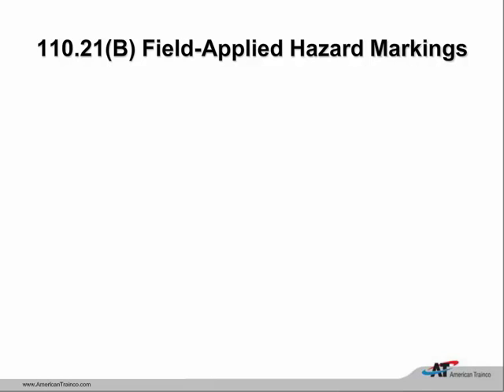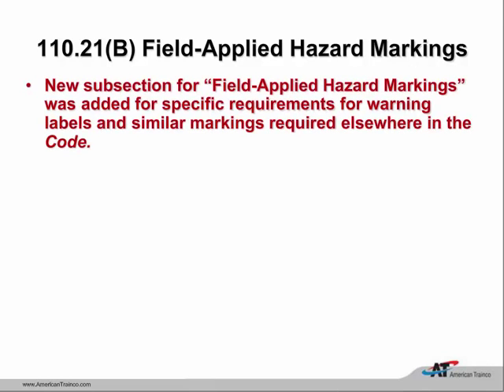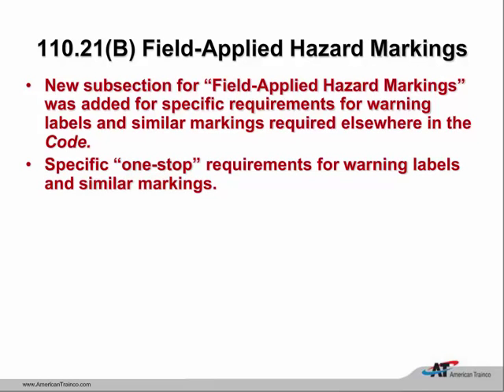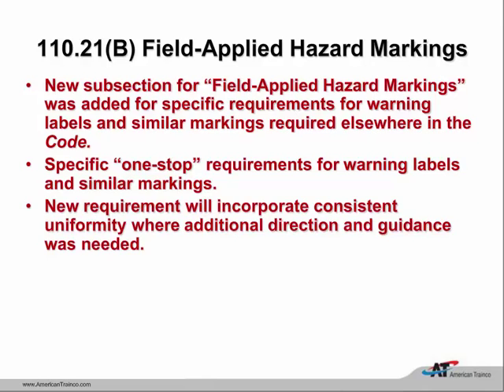In conjunction with 110.16, we saw 110.21B as a global change: field applied hazard markings. This is definitely going to coincide with the ANSI standard Z535 for labels. This now covers any label—not just arc flash hazards. It might be a voltage hazard or any hazard in your facility. One-stop shop is what they'd like to see for all warning labels: consistency in font size, colors, and wording, to bring uniformity to all the different labels we have out there.